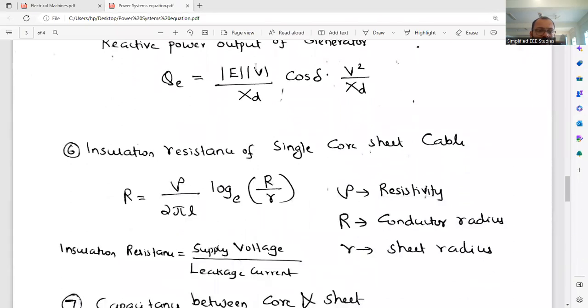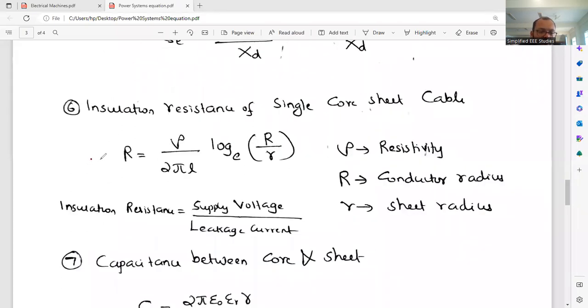Now you can calculate the insulation resistance. How to calculate the insulation resistance? R is equal to rho by 2 pi L into log of capital R by small r. Capital R is the sheath radius, small r is the conductor radius, and rho is the resistivity. Similarly, one more formula you can use in terms of leakage current: supply voltage by leakage current is nothing but insulation resistance.